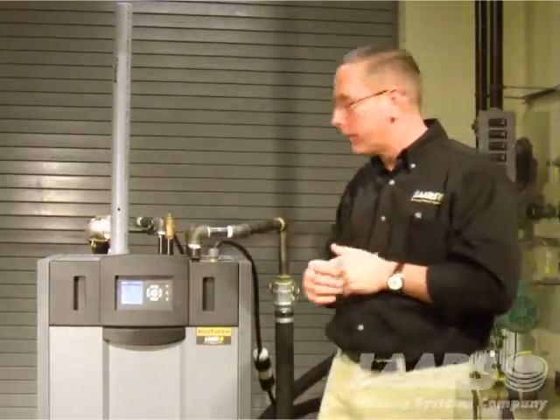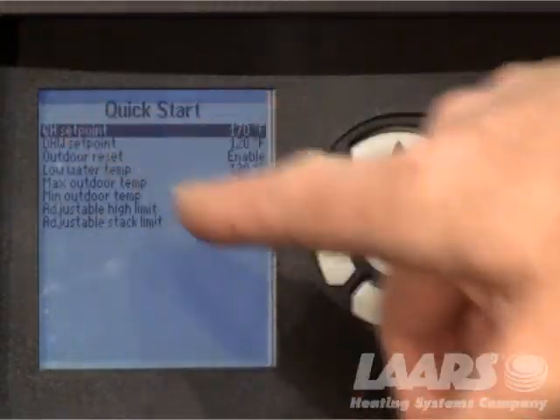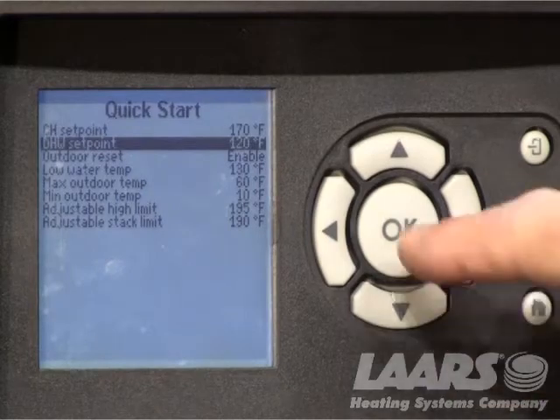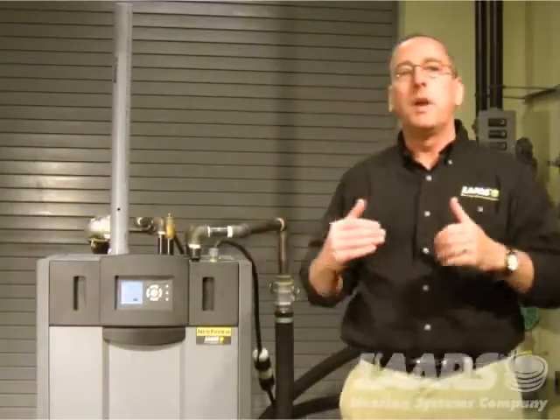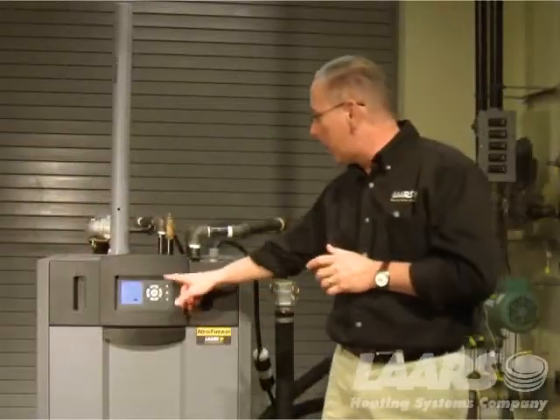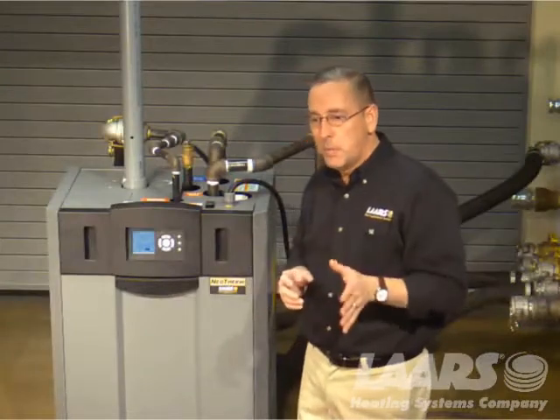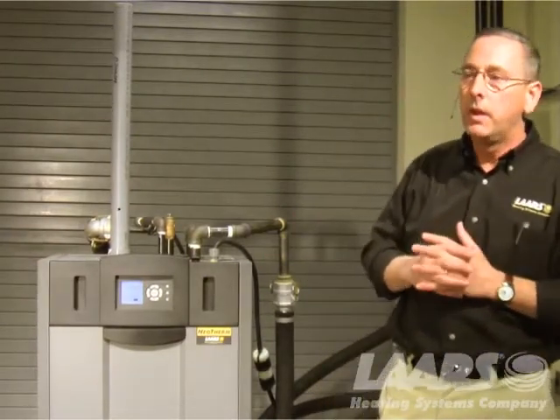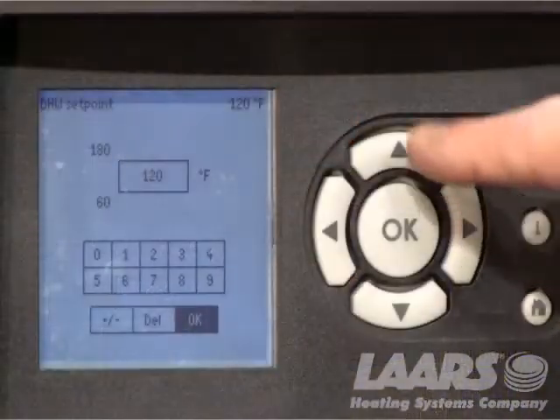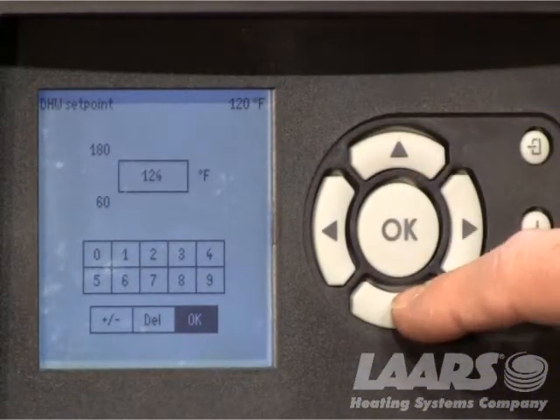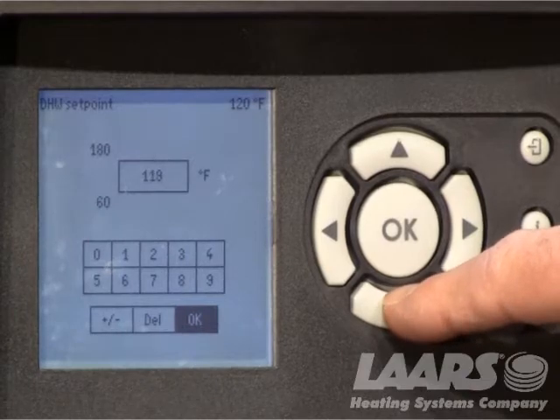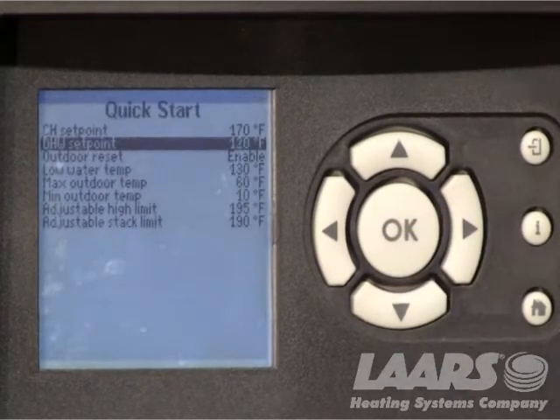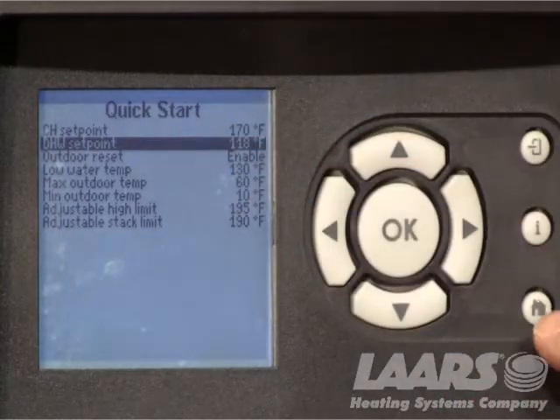If I have an indirect tank and I want to adjust the set point of my indirect, I come down and highlight DHW, press okay, and now I can adjust my tank temperature from my indirect simply by using the up or down arrows and press okay. Keep in mind you don't want to run too hot for scald reasons, and you should have an anti-scald or a mixing valve installed off your indirect feeding your faucets and things of that nature. You can simply use the up or down arrows to increase or decrease your temperature, press okay, and now you're back. Your settings are logged in.